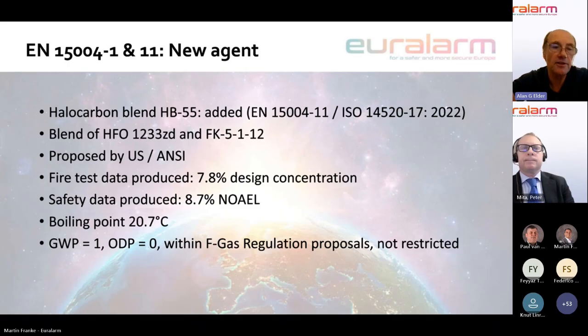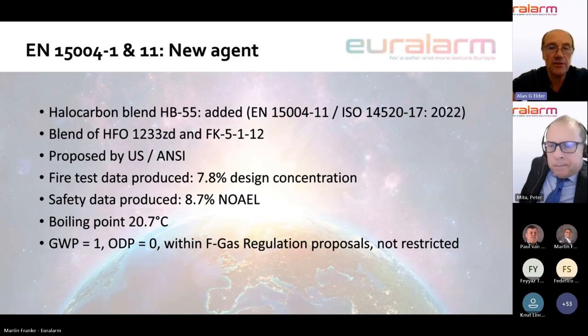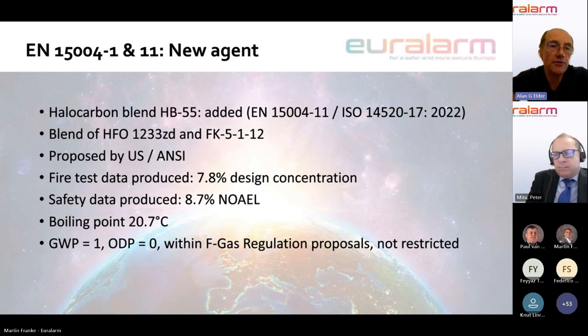And those two components in this case are HFO 1233ZD and FK5112. And they're introduced in equal measures of 50% of each of those. This was a proposal that originally went into the ISO standard by the US. Fire data was produced given a design concentration of 7.8% and with safety data of 8.7 being an NOAEL. It's got a boiling point of 20.7 degrees C, GWP of 1, 0 ozone depletion potential, and it is, like other halocarbon agents, within the F-gas regulation proposals, but is not restricted.